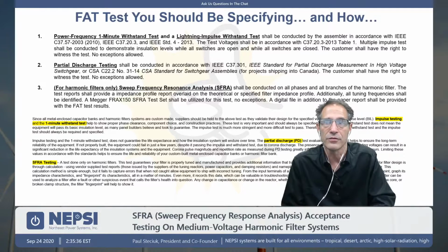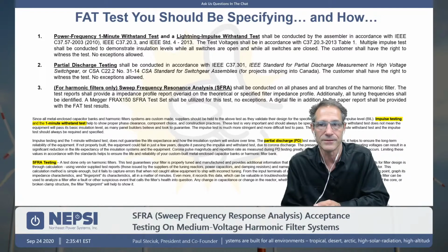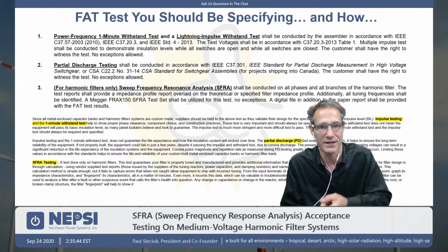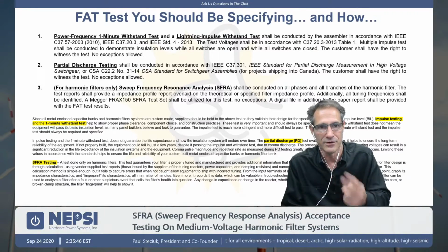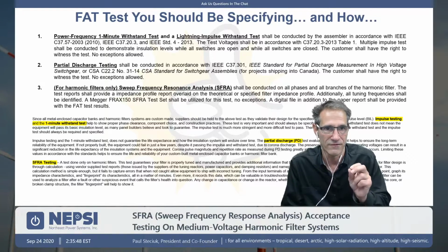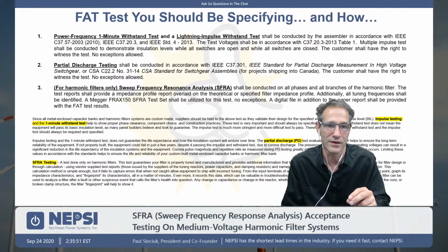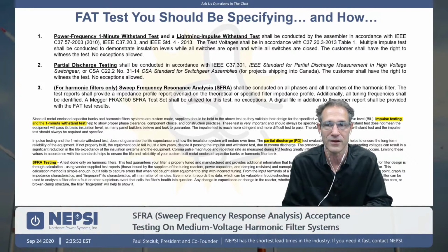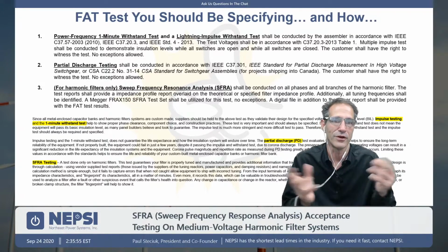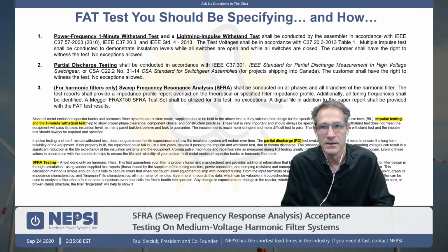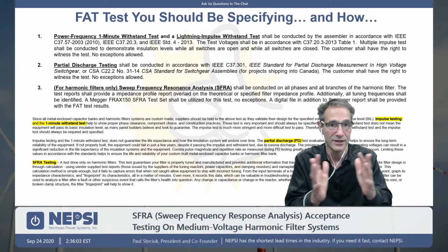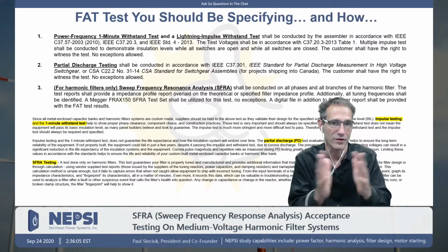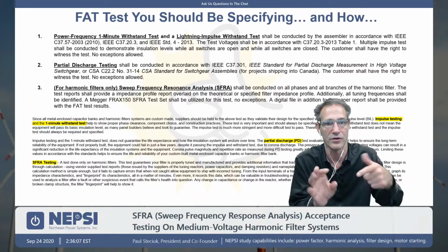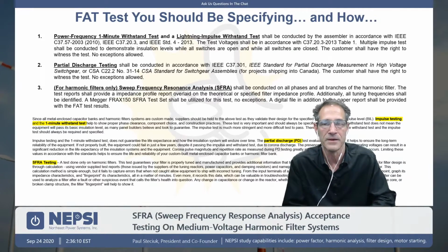There are some other tests, and we're going to be doing these in the future: the power frequency 1-minute withstand test and the lightning impulse test. Another 2 factory tests that we see as very important. We're going to do the impulse test, and I guarantee you're going to love that factory FAT test, because we will have a little bit of lightning going on. Also, partial discharge testing. Remember, impulse testing helps to guarantee that the design is correct. You get the right phase clearances and things like that. You don't have a bolt that's maybe passed through too far.